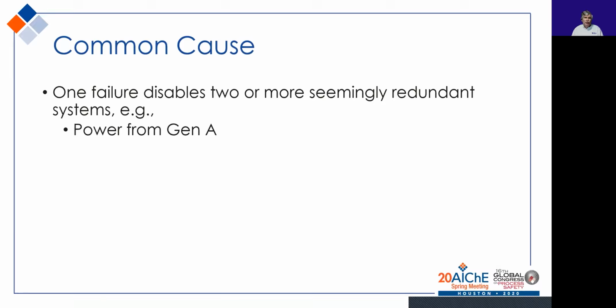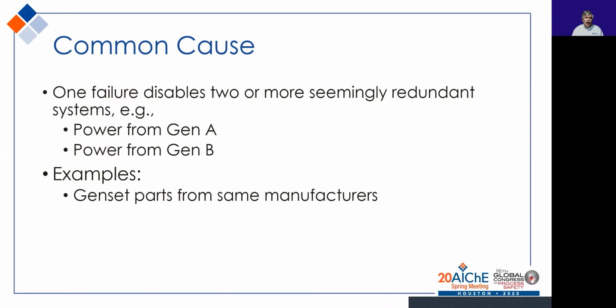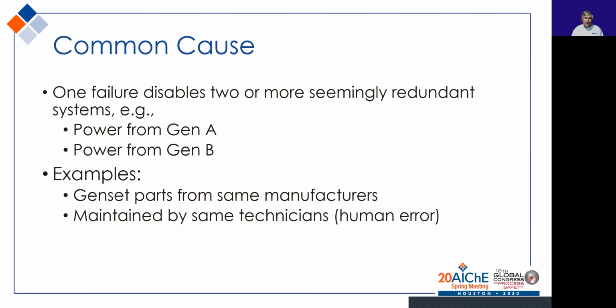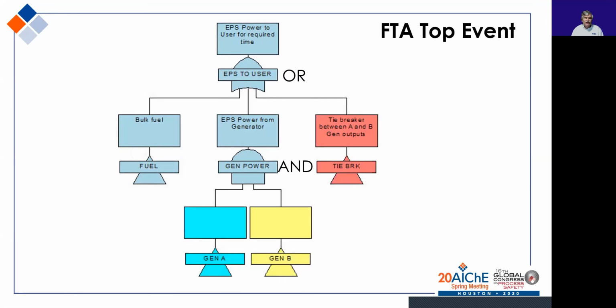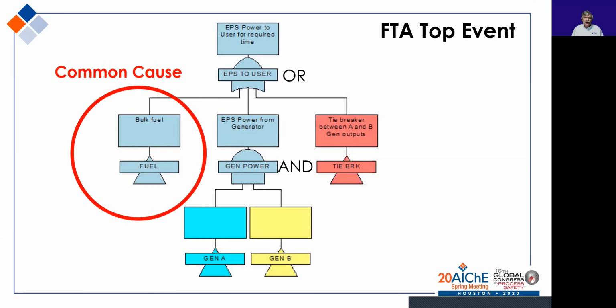For example, power from Gen A and power from Gen B are both disabled by the same problem. When genset parts come from the same manufacturers, the same manufacturing flaw could trip both generators. They're maintained by the same technicians, and they're operated in the same environment. We've already identified the bulk fuel system as a common cause because of the single tank and the power from one UPS for the 2 transfer pumps.